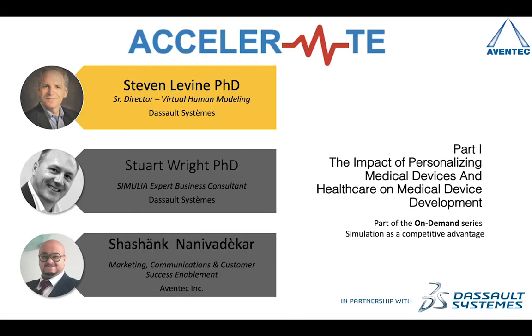Well, let me share at least the discussions that I've had with FDA folks about personalization, because it's a very challenging domain, particularly for the regulatory agencies. I guess it very much depends on the scope of the personalization, whether this is an infinitely personalizable device, for example, a digital pump, maybe a diabetes pump, where the frequency or scheme of regulation is tuned directly to the individual patient, and that's done on a learning basis. So that device changes over time. From a regulatory standpoint, how do you approve a device that's going to change after it goes to the market? So that's a particular challenge.